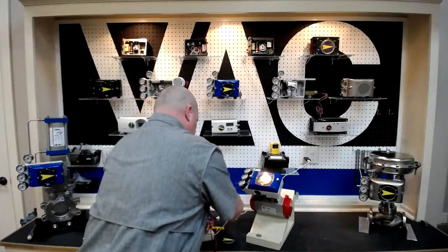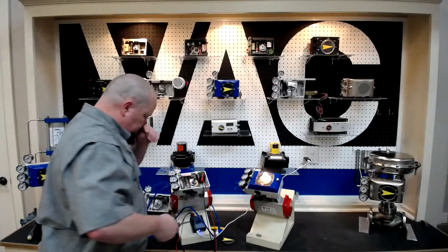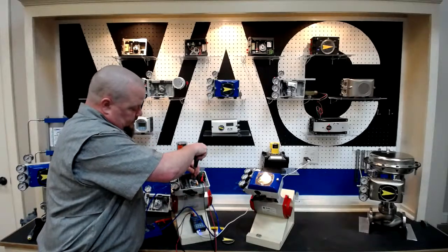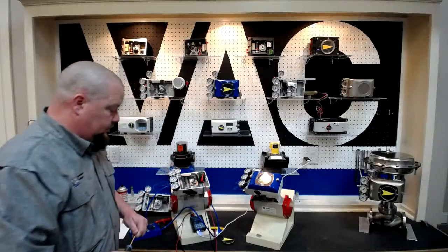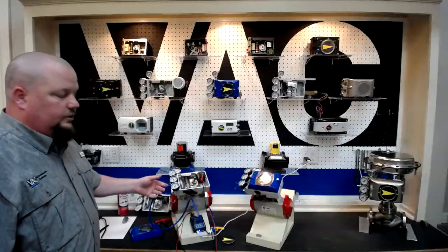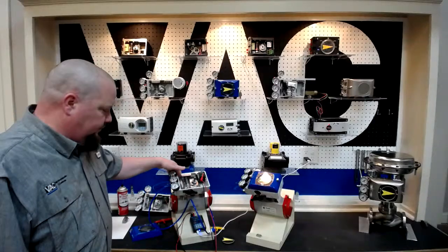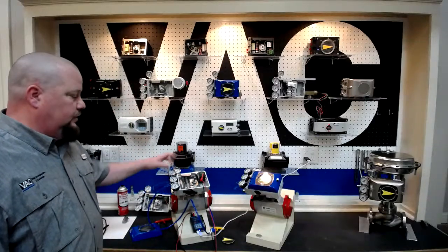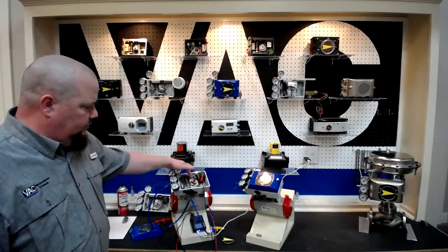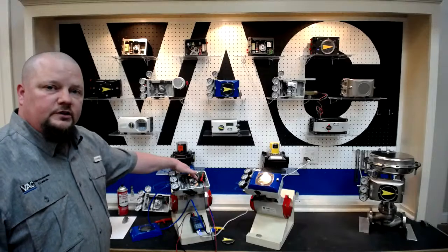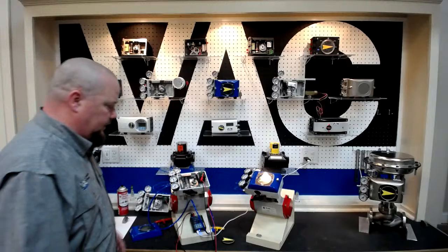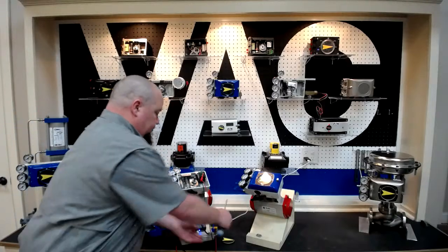is cut the air to the unit. And to show one quick thing is to make sure that this isn't the issue. When you tube the unit up, we're going to refer back to the first video. Once you put air on the unit, the best thing to do is reach inside and push the balance arm down, and you can see it'll show you at that point that you're jumping the cam. But if you skip that step, this is something you can come back and look at later. So I'm going to shut the air off.